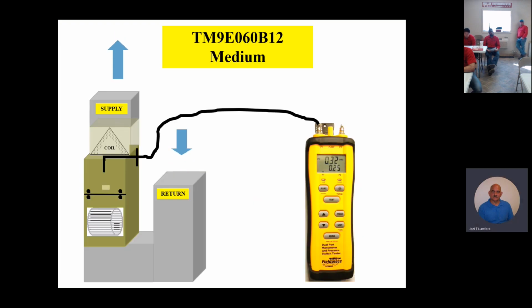Okay, so this one here, this particular furnace is a TM9E060B12 on medium speed tap. So find that on the chart. And by the way, if you guys will look at the graphic real quick, I want you to notice something on the furnace. This is real important. Look at my cursor. On the furnace, the coil is not included on that chart. So what you're going to do, you're going to sneak in underneath the coil and take static pressure as it comes off the fan, and just slide it underneath the coil if you can get it under the coil. So just remember, the coil is not included on that airflow chart on the furnace product.